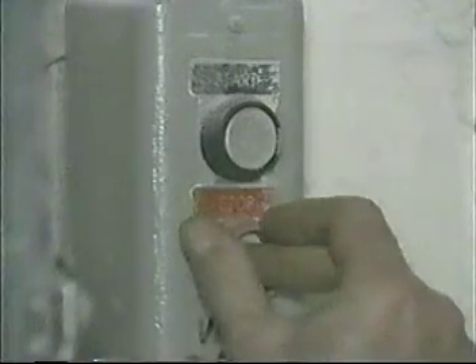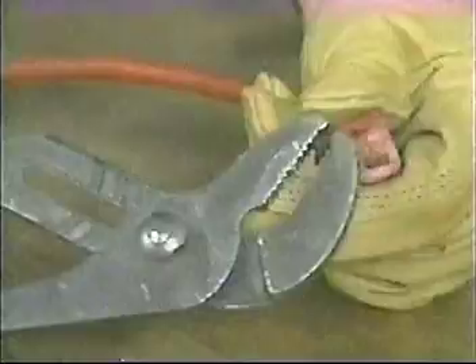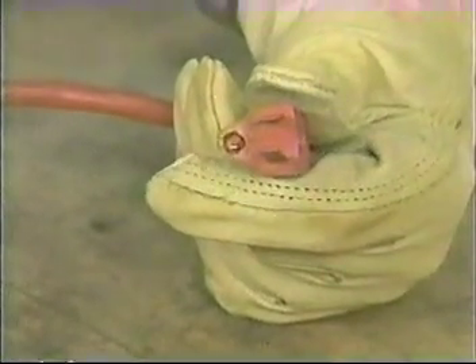Taking a shortcut, such as using an on-off control to de-energize a machine before making a quick repair, can be disastrous. There is always the possibility that it will be restarted by an automatic timing device or by someone who doesn't realize you're there. Removing the ground connection on a plug as a convenience is another dangerous practice because it significantly increases the risk of electrical shock.